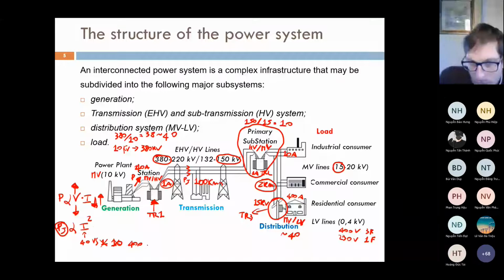But that's not an issue, because the low voltage lines are maybe, I don't know, 500 meters or even less, let's say 200 meters. So even if you have a very high current, you have to distribute it over just a very short distance, so the Joule losses are acceptable. So increasing the voltage here is not just for the losses, but also for the cross section of the cables or overhead lines, because the lower the current, the lower the cross section could be, so it is more economical.